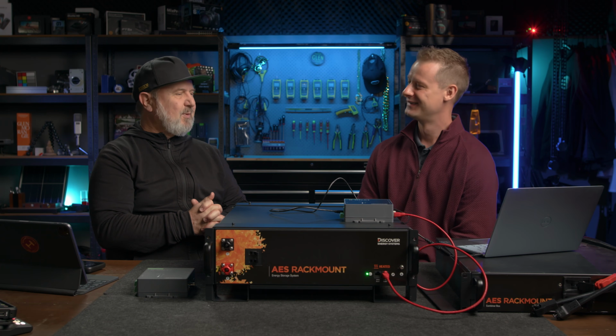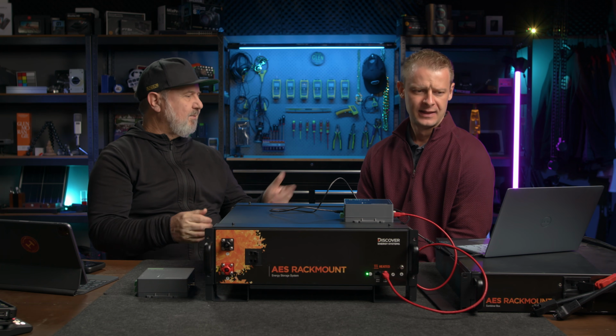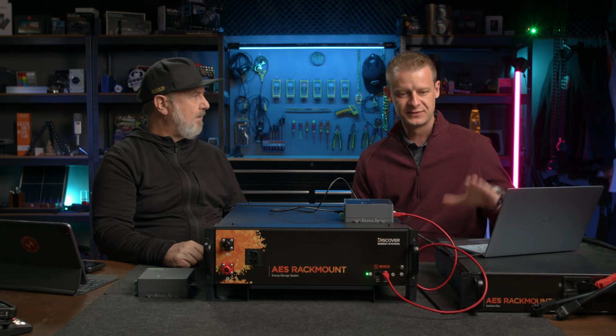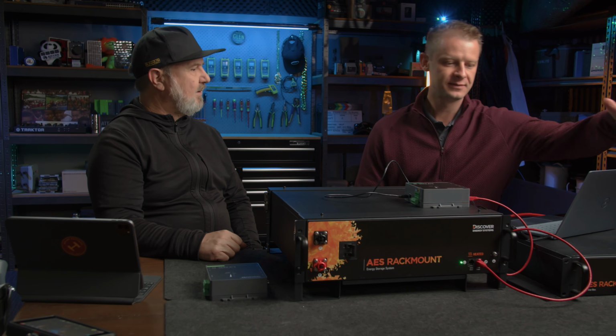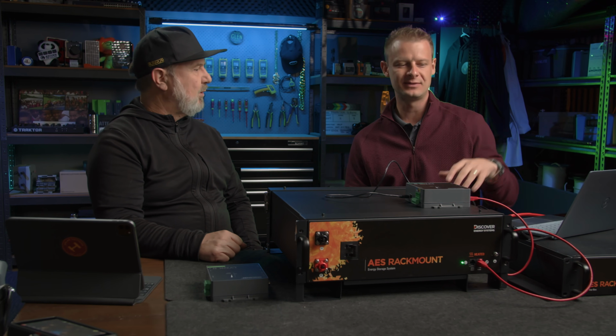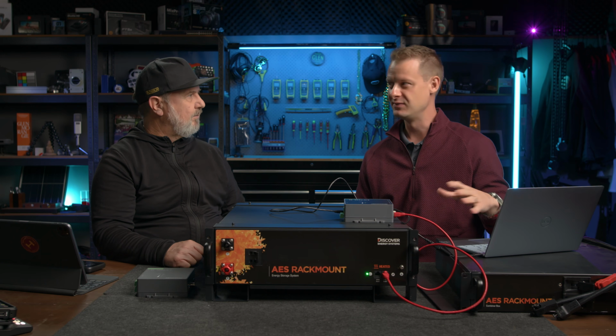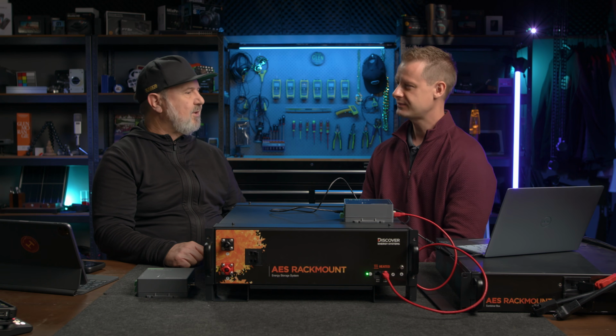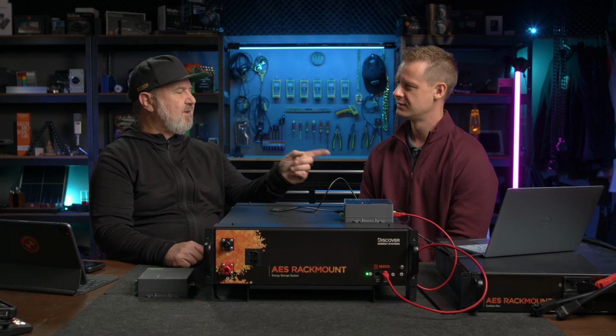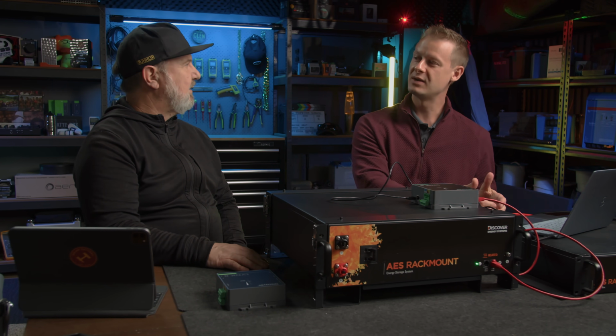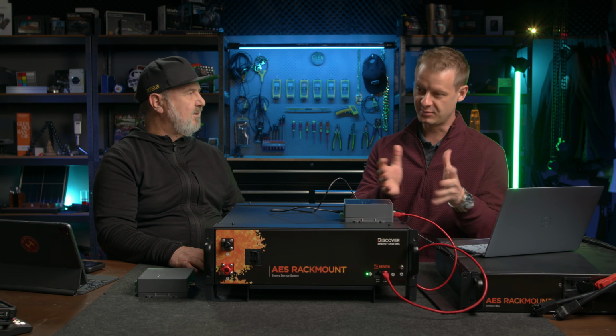Does a combiner box provide any other functionality apart from combining? Each battery is fused internally, and then we have a disconnect up front, mainly for convenience when servicing the product. So turning off the combiner box will turn off the 6 batteries connected to it? It won't - the batteries remain on, but it disconnects your power electronics from the batteries themselves.